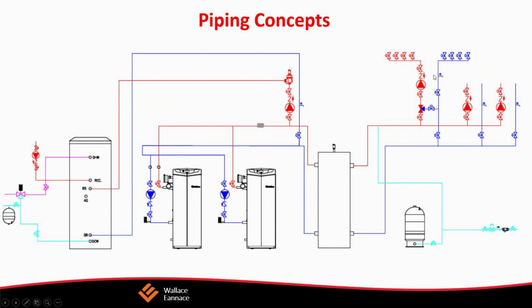This is an actual drawing that we did for an actual installation. All of these drawings that you're going to see are like that. Again, primary secondary piping, and then you can see how we pump away from the expansion tank each and every time. Same situation here, similar situation, effectively the same orientation here.